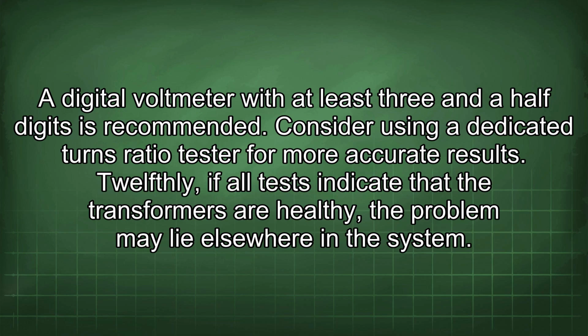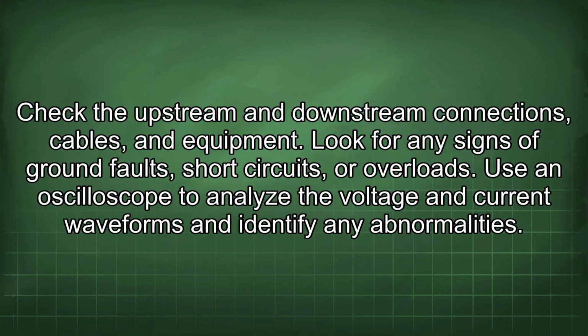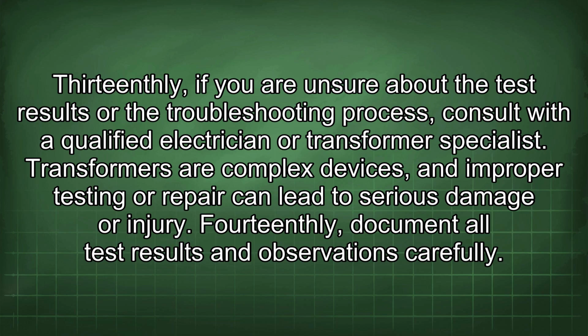12thly, if all tests indicate that the transformers are healthy, the problem may lie elsewhere in the system. Check the upstream and downstream connections, cables, and equipment. Look for any signs of ground faults, short circuits, or overloads. Use an oscilloscope to analyze the voltage and current waveforms and identify any abnormalities. 13thly, if you are unsure about the test results or the troubleshooting process, consult with a qualified electrician or transformer specialist. Transformers are complex devices, and improper testing or repair can lead to serious damage or injury.